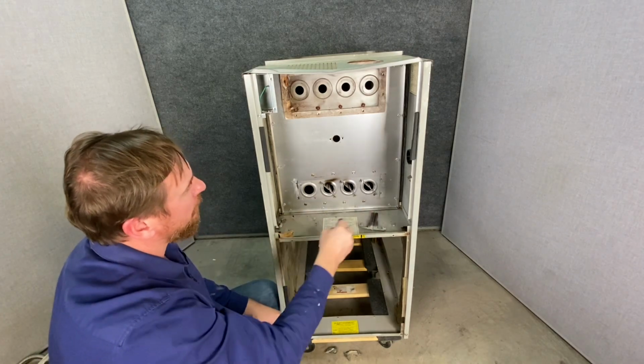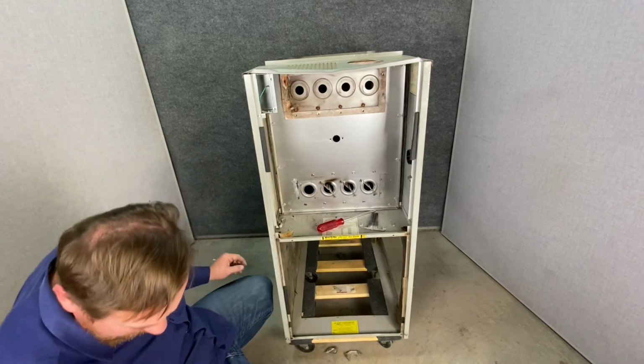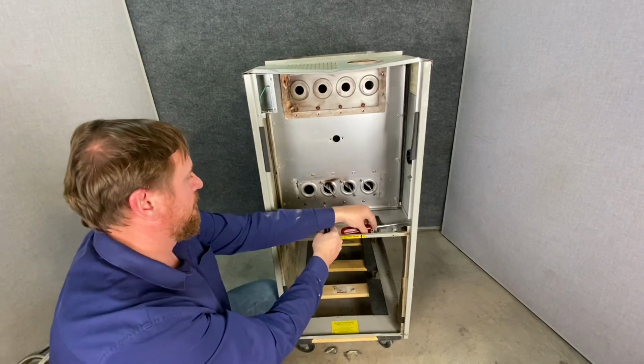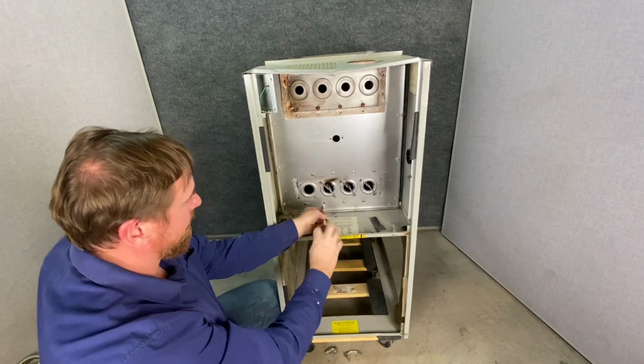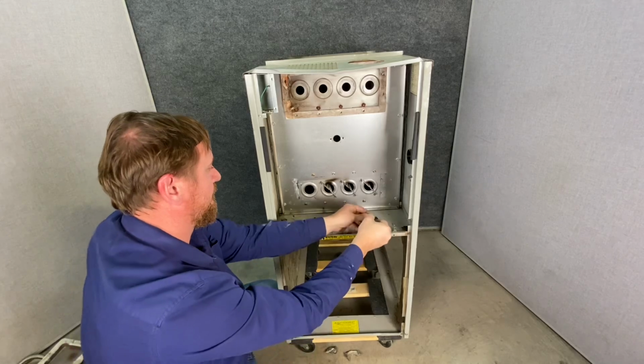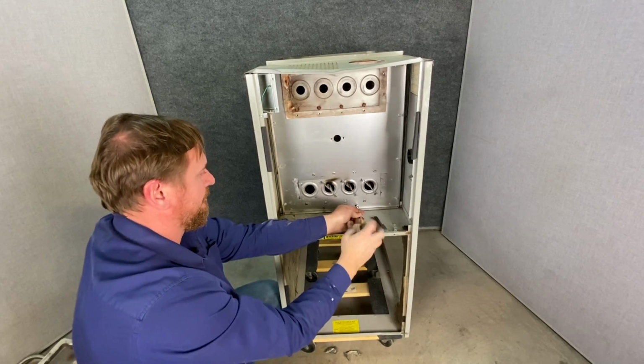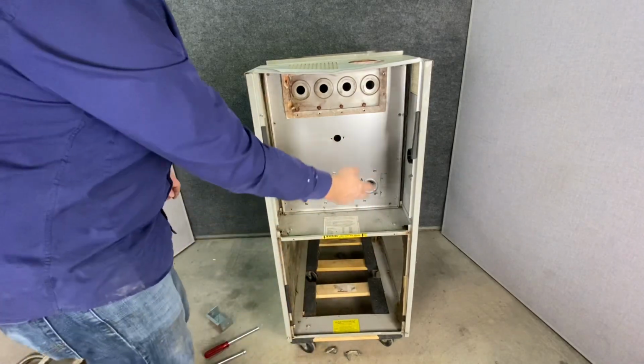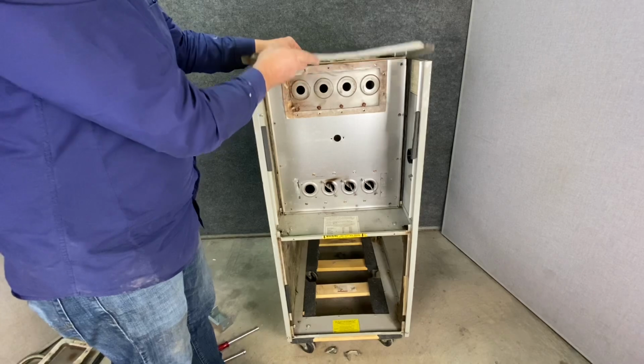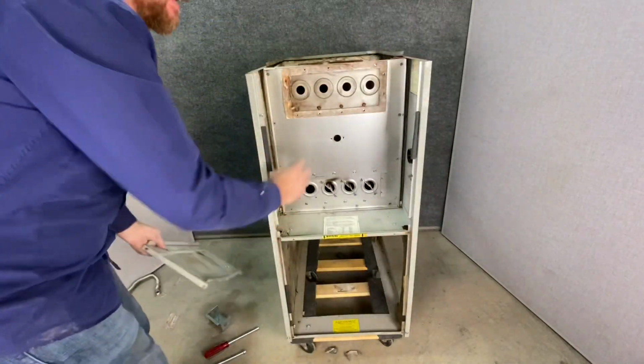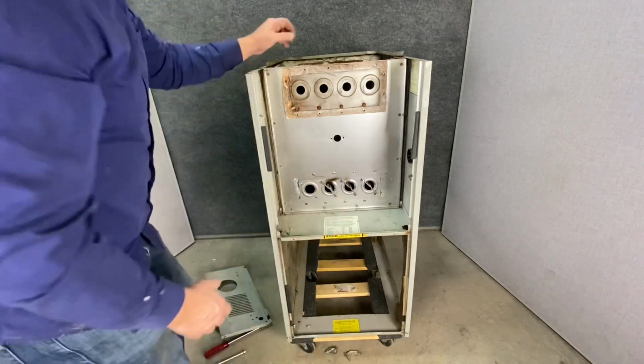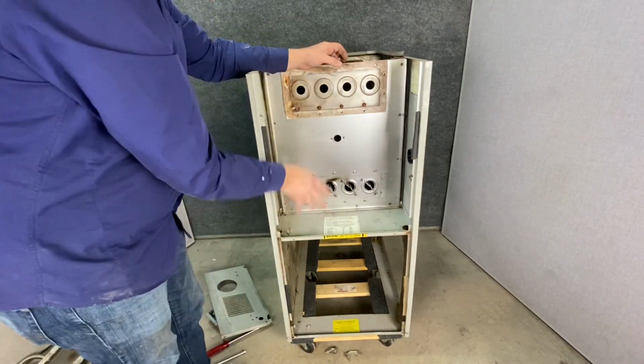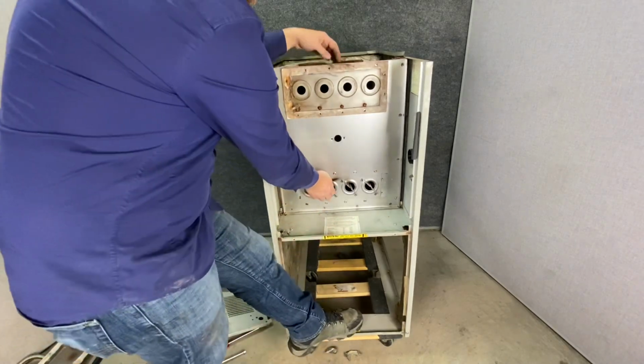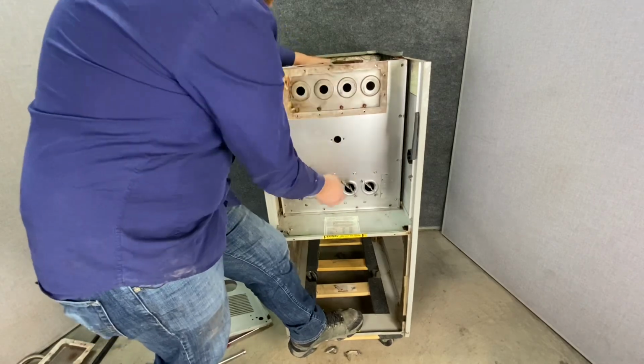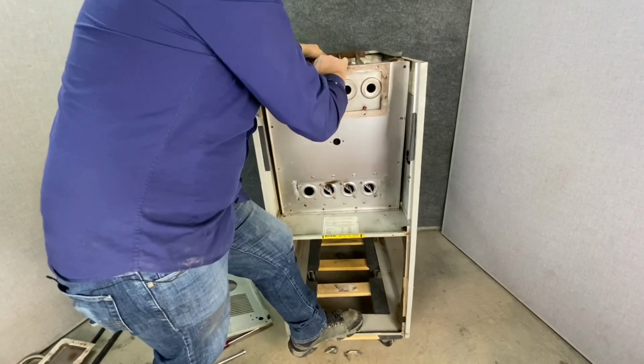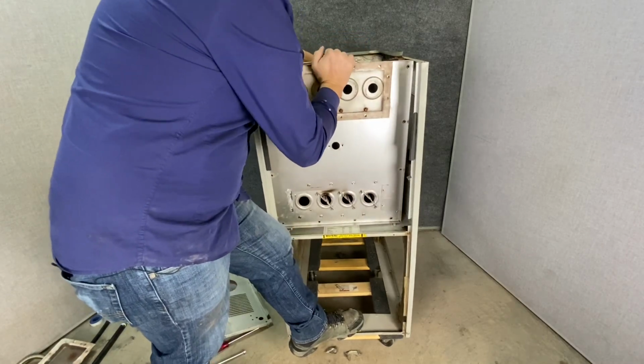Next, what we're going to do is pull all of the screws out for this heat exchanger so we can pull the heat exchanger out of this unit and take a better look at it. Now that we have all the screws taken off from this furnace, I even took this top plate off so it's a little easier to get to. Comes off nice and easy. Now this is our heat exchanger. This is the heart of the entire system. So imagine if this was in a closet, you'd have to take all of these components off to get to this point. You could leave the blower section, but it's still a pretty good bit of work. Now you have to pull this out.